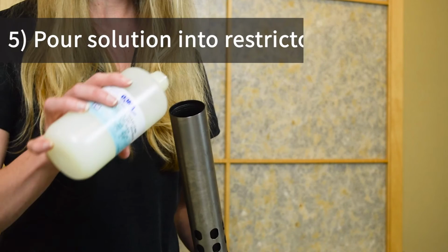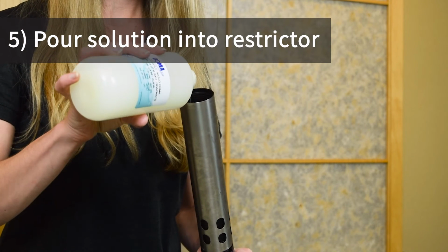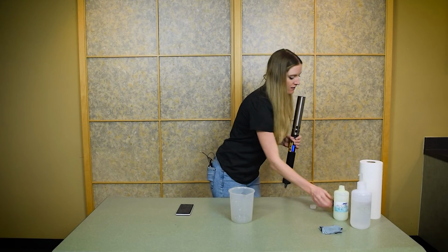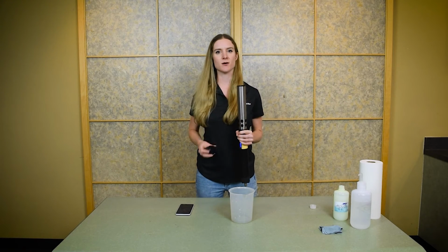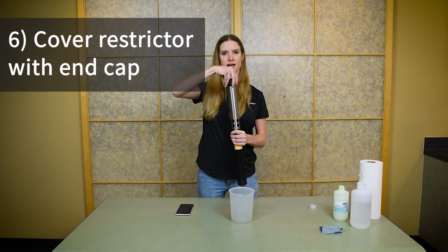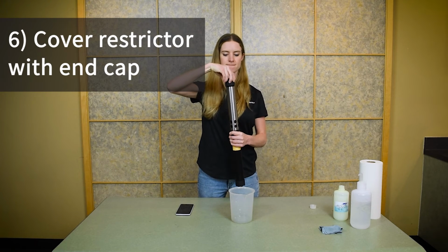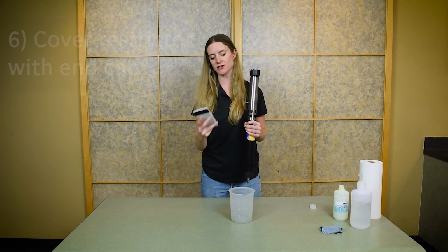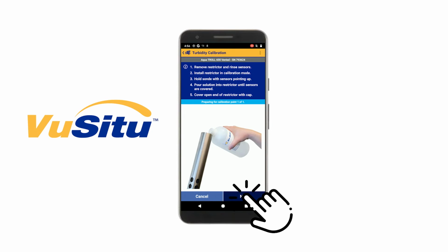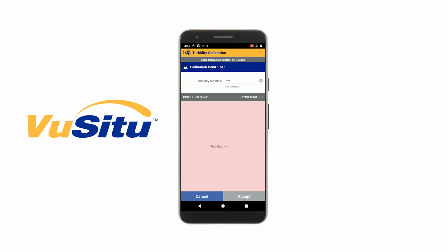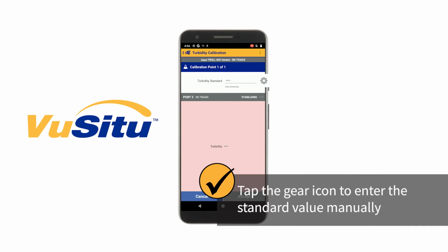Pour fresh In-Situ turbidity solution into the restrictor until the sensors are covered. Once you have solution about 1 centimeter above the sensors, cover the restrictor with the end cap, and then start your calibration in VuSitu. VuSitu will auto-detect which calibration solution you're using. Tap the gear icon if you need to enter the value manually.